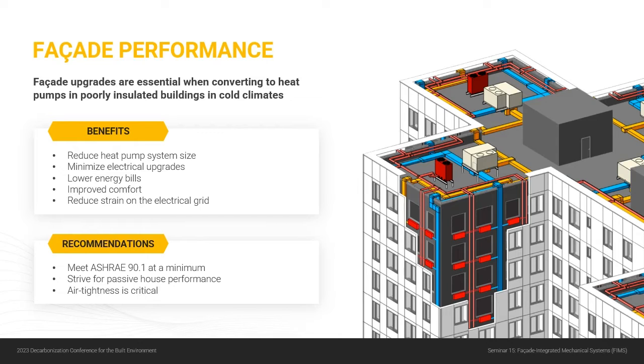It also improves comfort, and when you're looking at the big picture, it also reduces strain on the electrical grid. So some basic recommendations would be to meet ASHRAE 90.1 at a minimum for the facade performance, but if you can get to passive house or somewhere close to that, then that's definitely even better. And it's not just about R values and U values. The air tightness is really critical here because we don't want outside air infiltrating into that cavity space.